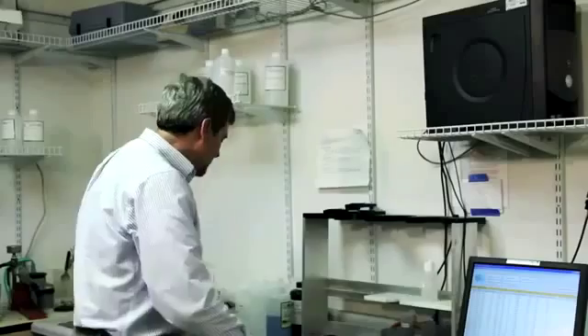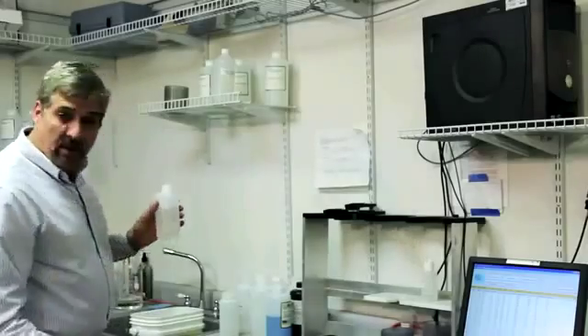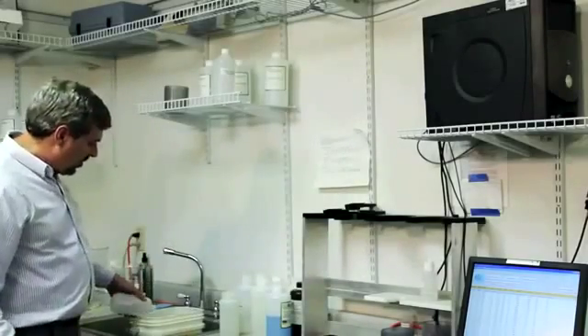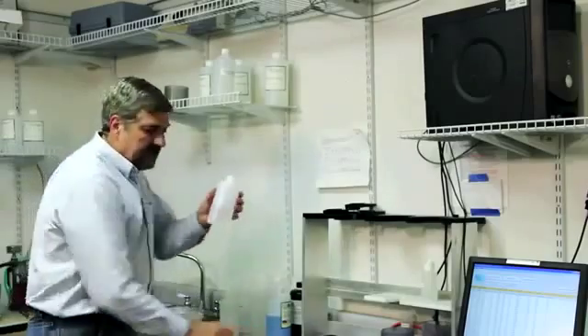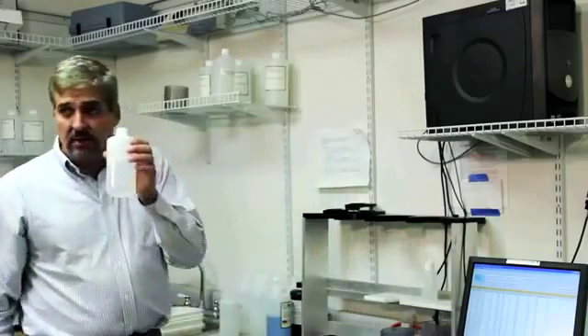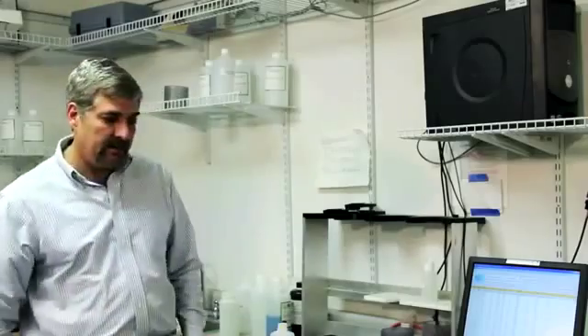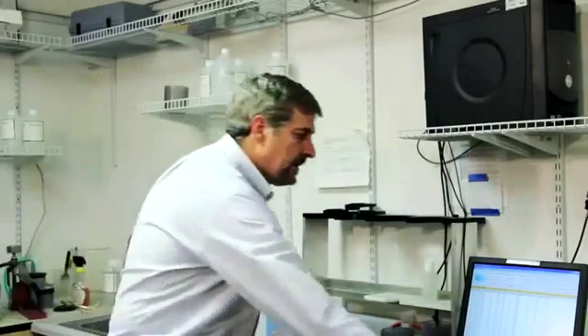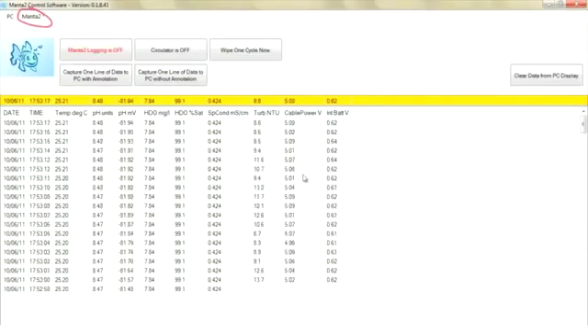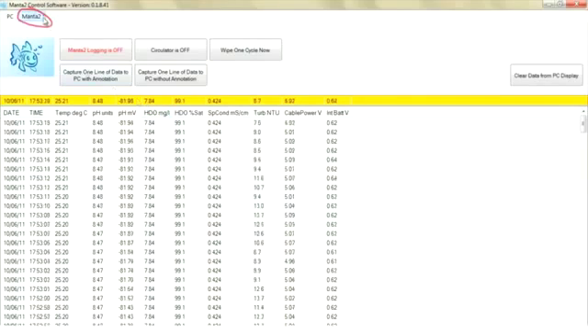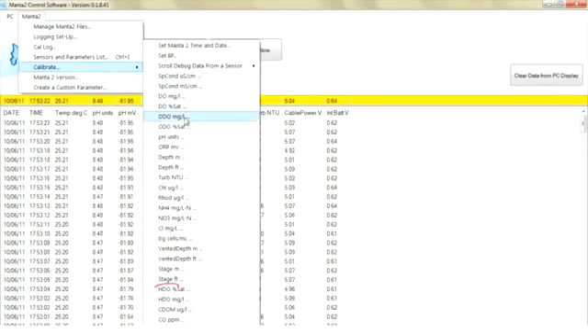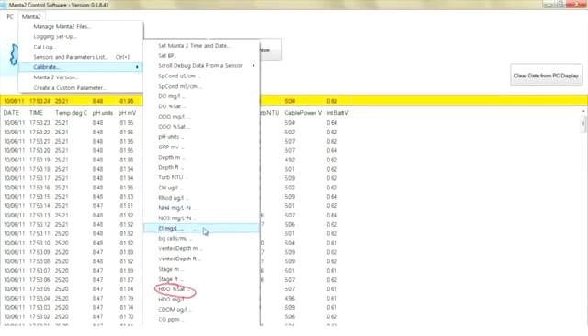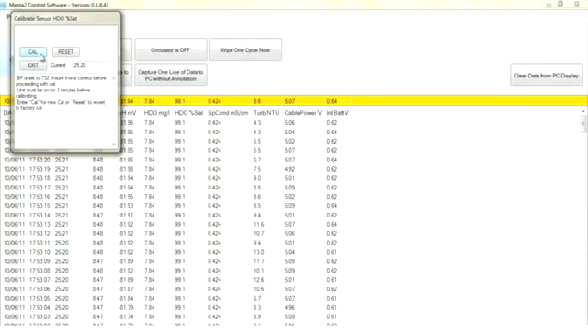Now for dissolved oxygen. I'm going to use my DI water, or I could use tap water. I'm going to take a bottle, whether it be a one liter bottle or a half liter bottle like I have here. Fill it half way full. Shake vigorously for one minute. Remove the lid. Let it stand for a minute.